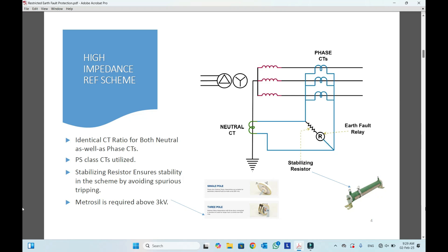Its name is restricted earth fault. It is a little bit different from the normal earth fault. In normal earth fault, if an earth fault occurs, the dedicated relay for earth fault protection will operate, but it will not tell the location of the earth fault. It will not give any information about the zone. For example, if there is a power transformer with high voltage and low voltage winding feeding a distribution system, there is a chance that the earth fault protection of the transformer, feeder, or incomer will operate, but this will not confirm 100% the location of the earth fault. In this case we need restricted earth fault protection, which works only for specific zones.